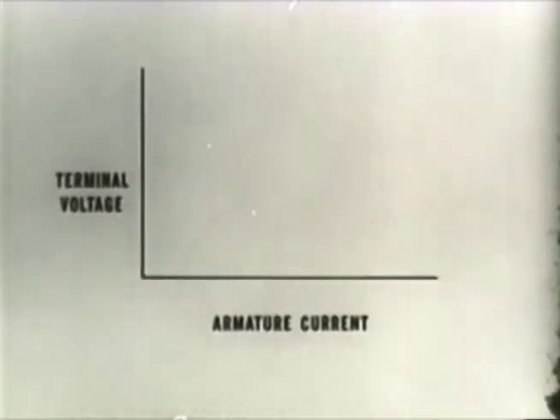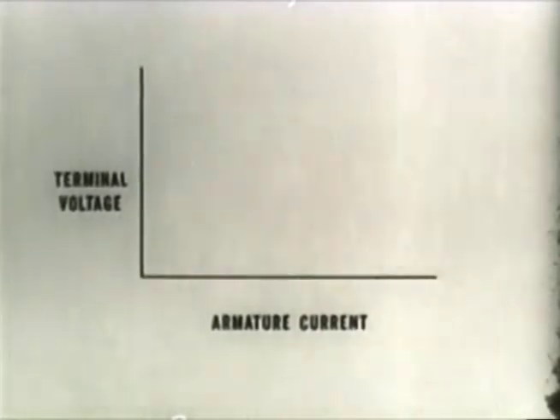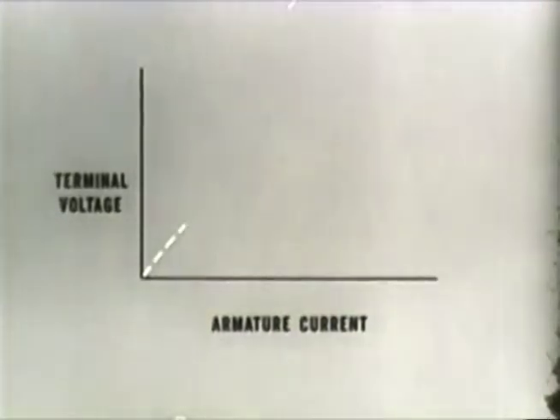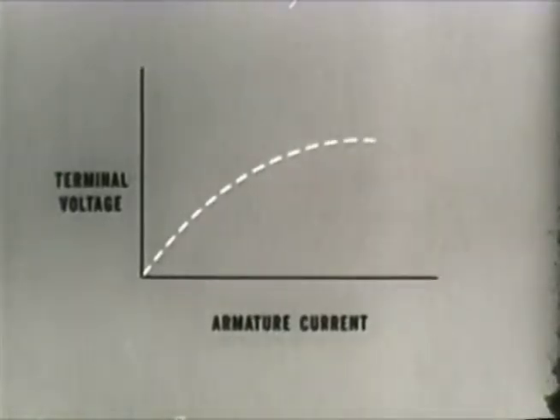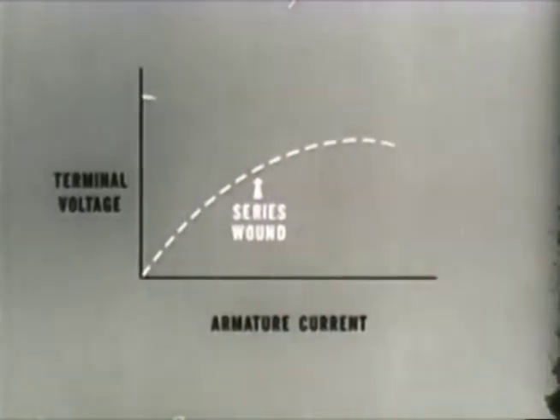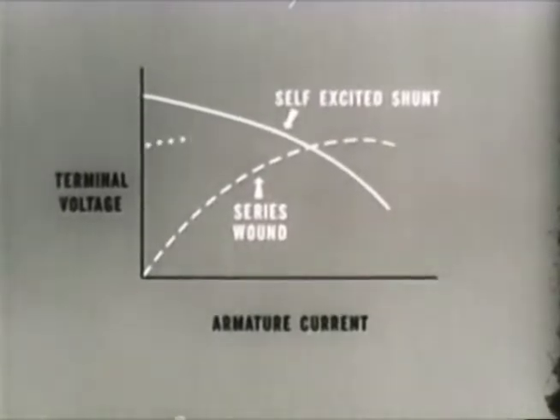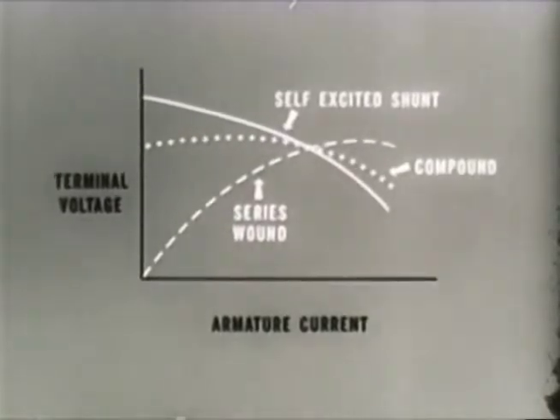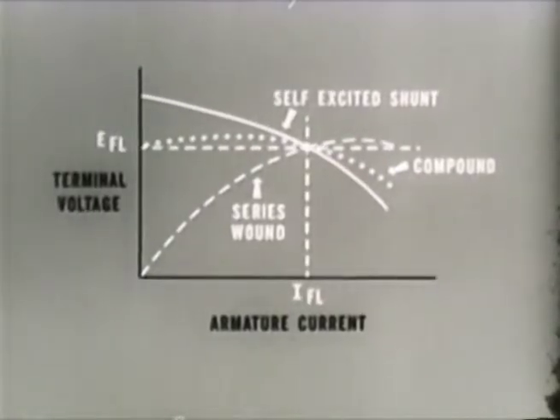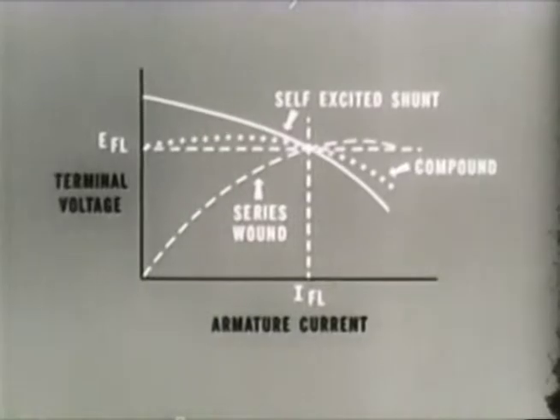A graphic representation of generator output characteristics with terminal voltage plotted vertically and armature current horizontally shows that the output of the series-wound generator has very poor voltage regulation. In parallel or shunt-wound generators, the voltage regulation is fairly good but current regulation is poor. Compound-wound generators offer a flat compounded output that is normally most desirable — it combines the good features of both the shunt and series-wound generators and provides stable voltage output under changing loads.